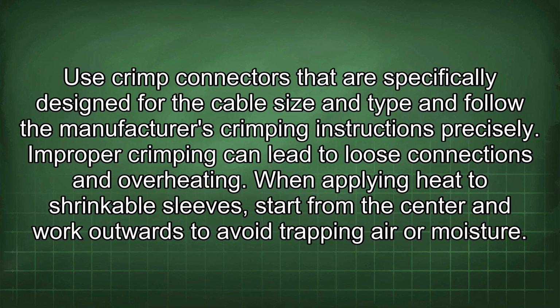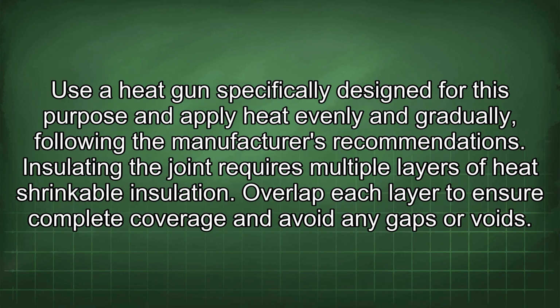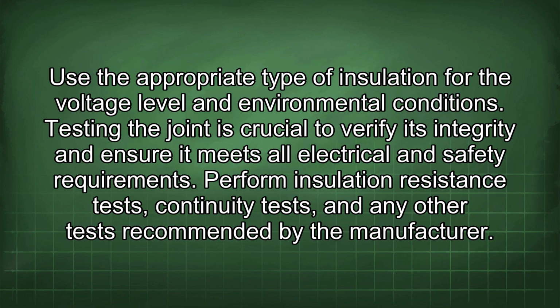When applying heat to shrinkable sleeves, start from the center and work outwards to avoid trapping air or moisture. Use a heat gun specifically designed for this purpose and apply heat evenly and gradually, following the manufacturer's recommendations. Insulating the joint requires multiple layers of heat-shrinkable insulation. Overlap each layer to ensure complete coverage and avoid any gaps or voids. Use the appropriate type of insulation for the voltage level and environmental conditions.